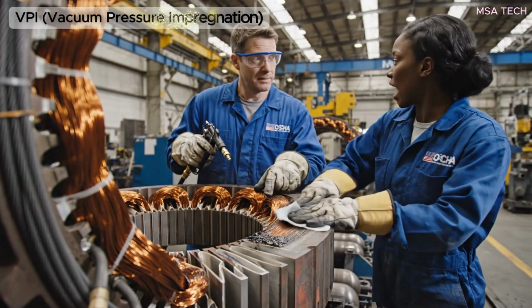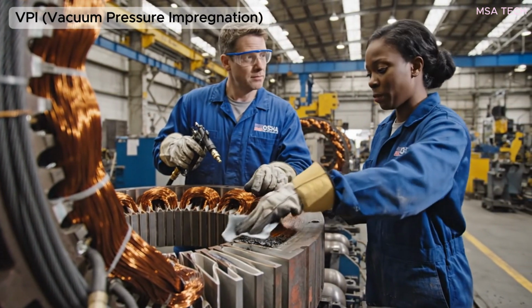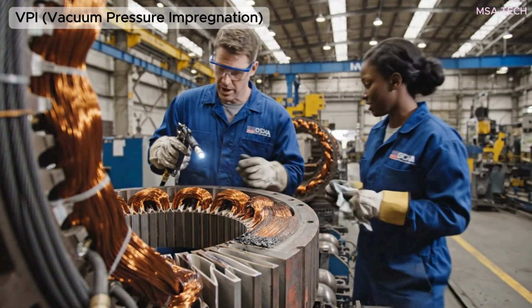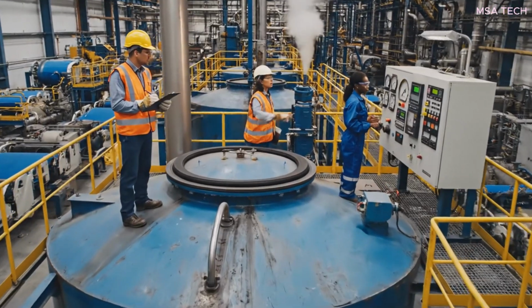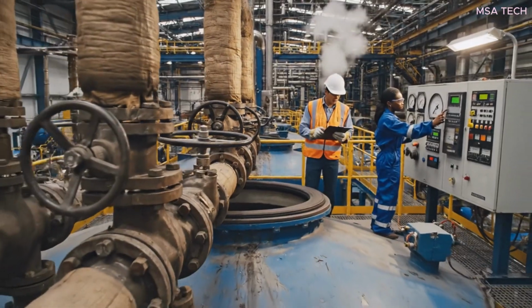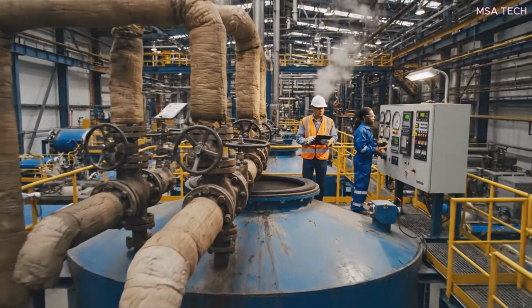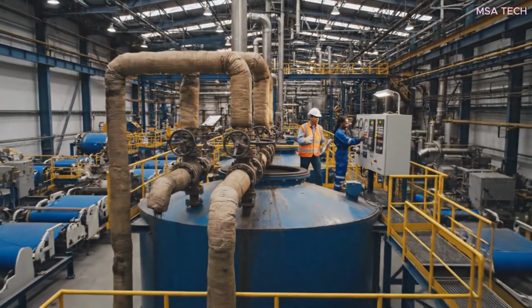Make sure we get all the dust out of these windings before we wipe it down. Absolutely. Any residue left will compromise the VPI process. Looks good. The vacuum levels are stable at 20 torr. Check the resin viscosity next. It's within specification. Safety checks are complete.